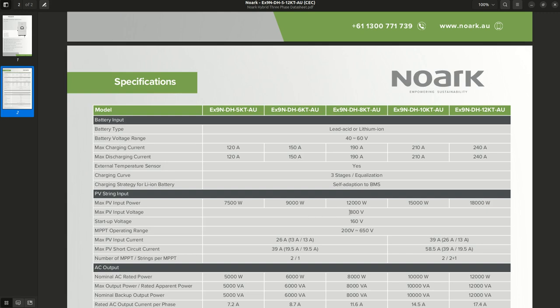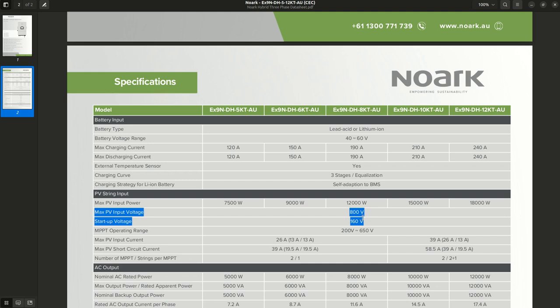Minor note to my last video where I engineered a complete off-grid system and looked at every parameter. Here's one I didn't look at because I just assumed it. Here's the three-phase model which can go right up to 800 volts. In Australia, the residential limit is 600 volts. Either way, I can still get to maximum PV array size.